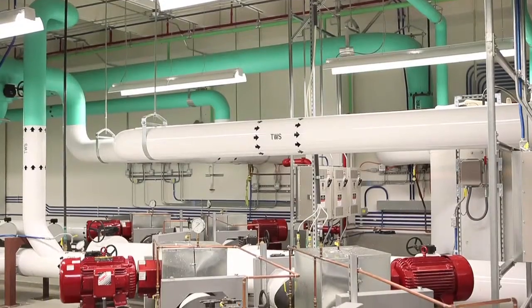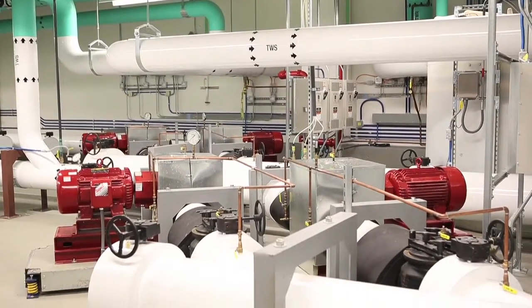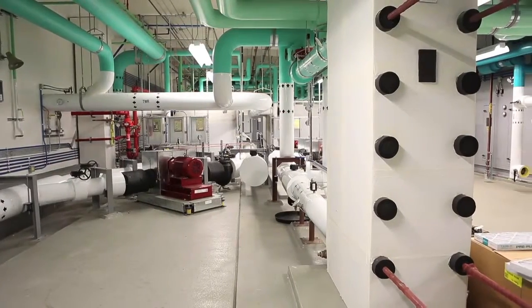We set a PUE, power use effectiveness, of 1.06, the best in the world. That means 1 unit of energy goes to computing, and 6% of that goes to everything else, to cooling the system, to providing fresh air, lighting, energy conversion from grid power to chip power. And to be able to meet that 1.06 PUE, you have to pay very close attention to everything that uses energy. So any of the pumps, fans, etc., you need to minimize all the non-compute energy.